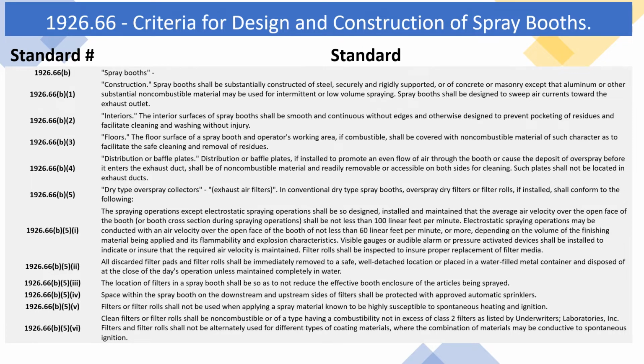1926.66 B.5.i. The spraying operations, except electrostatic spraying operations, shall be so designed, installed, and maintained that the average air velocity over the open face of the booth, or booth cross-section, during spraying operations shall be not less than 100 linear feet per minute. Electrostatic spraying operations may be conducted with an air velocity over the open face of the booth of not less than 60 linear feet per minute, or more, depending on the volume of the finishing material being applied and its flammability and explosion characteristics. Visible gauges or audible alarm or pressure-activated devices shall be installed to indicate or ensure that the required air velocity is maintained. Filter rolls shall be inspected to ensure proper replacement of filter media.